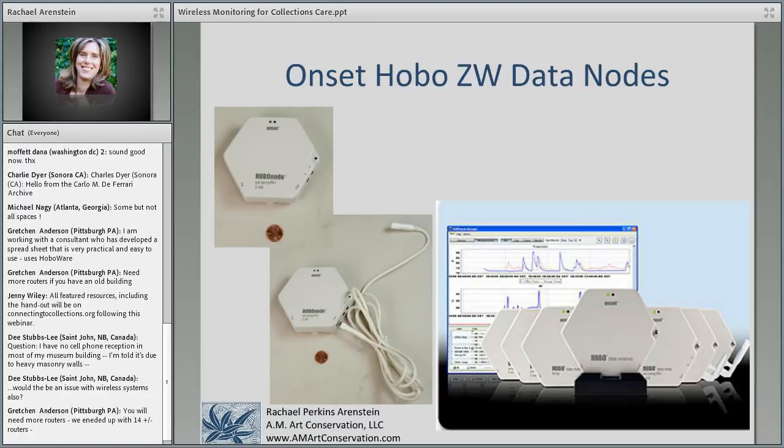So for instance, the HOBO nodes have a 4,000 sample memory, but if you are logging temperature and relative humidity, you already have to cut that number in half. So your 4,000 samples actually become 2,000 temperature and RH points. So if you're then monitoring, let's say, every 15 minutes, that's going to give you 96 samples throughout the day.